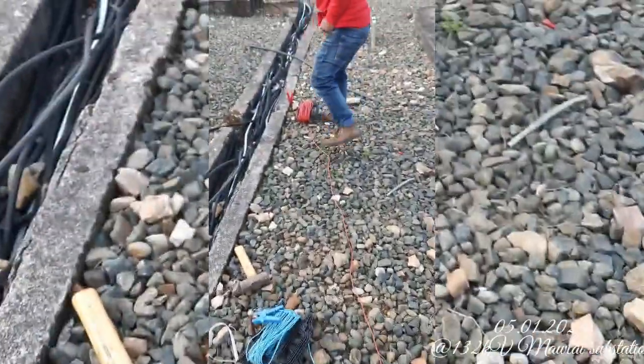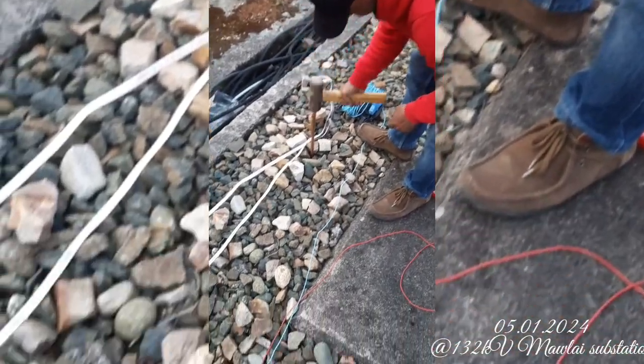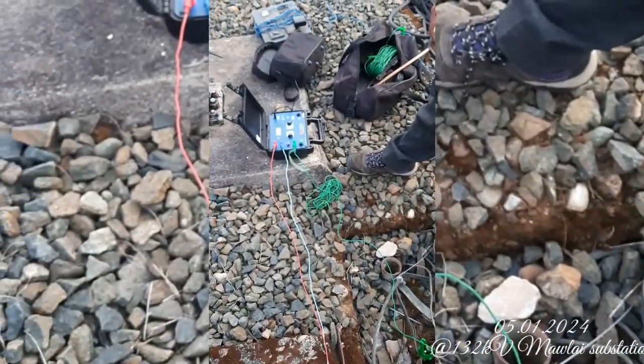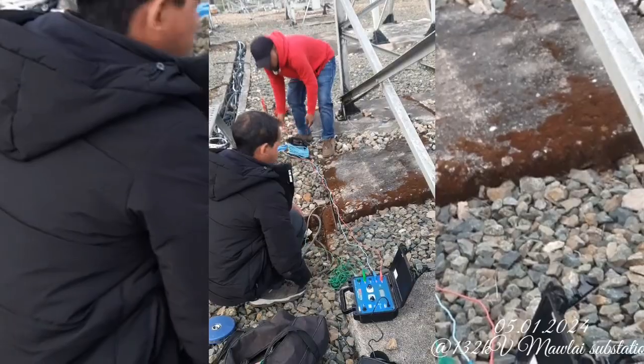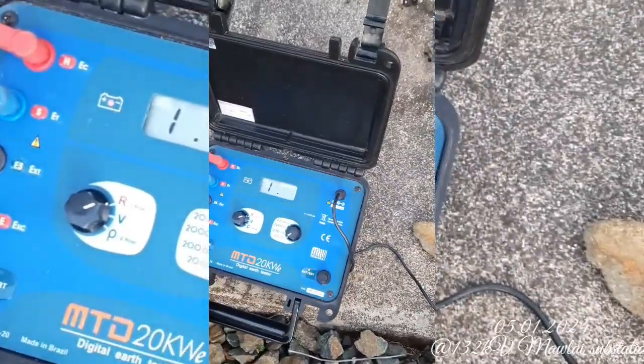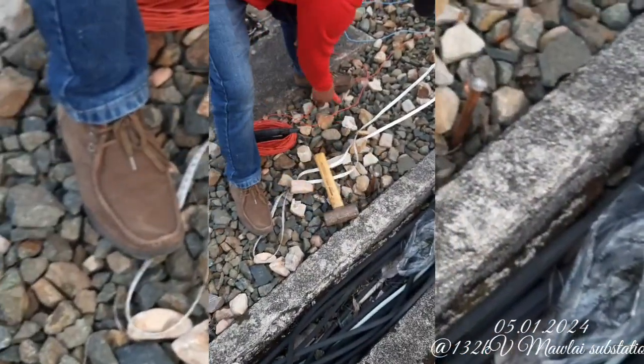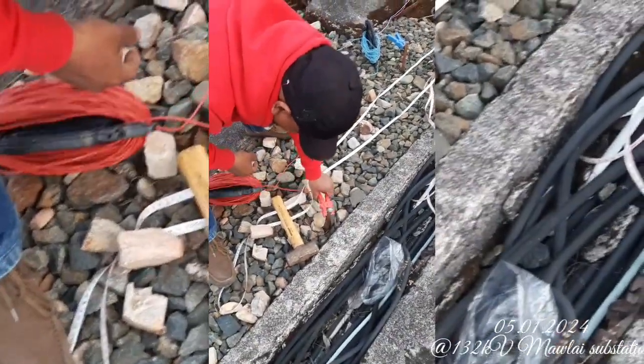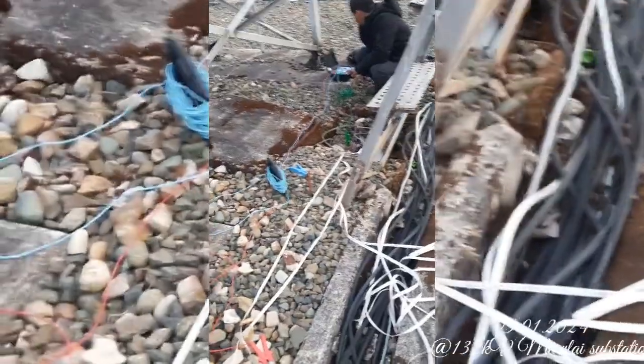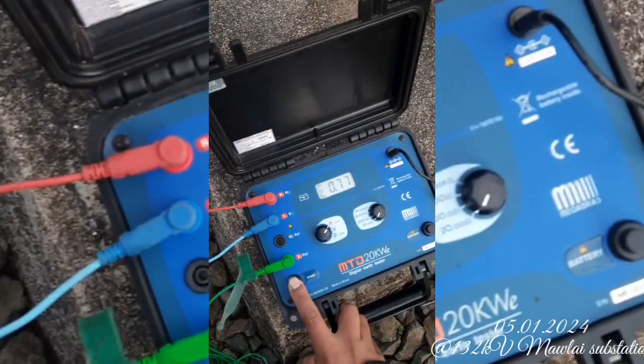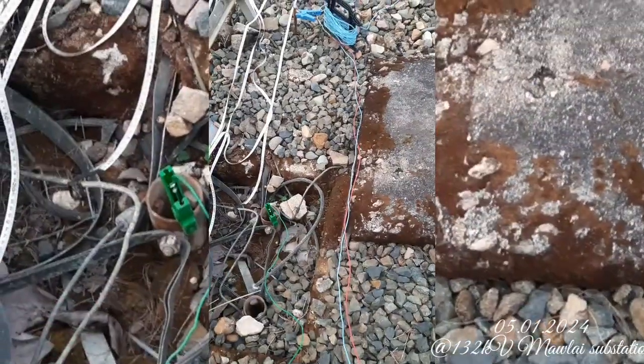Now if I keep on reducing the distance, keeping it at 5 meters and 2.5 meters, let's see. In our case, 2.5 is our voltage electrode and 5 is our current electrode. Let's see the reading. It will be slightly on the higher side because the distance is quite important. So our reading is going up, now it's 0.77.